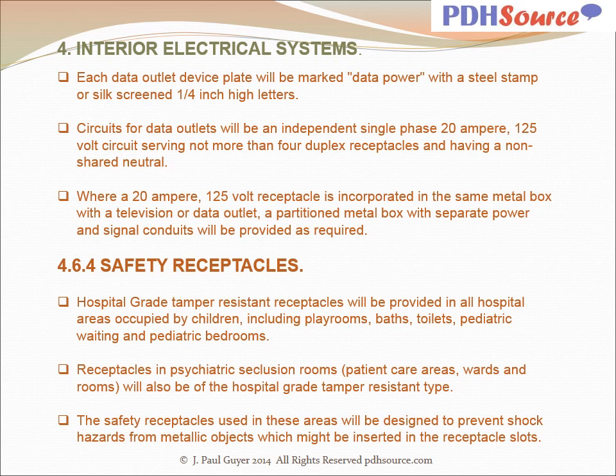Each data outlet device plate will be marked data power with a steel stamp or silk screen quarter inch high letters. Circuits for data outlets will be an independent single phase 20 amp 125 volt circuit serving not more than four duplex receptacles and having a non-shared neutral. Where a 20 amp 125 volt receptacle is incorporated in the same metal box with a television or data outlet, a partitioned metal box with separate power and signal conduits will be provided as required.